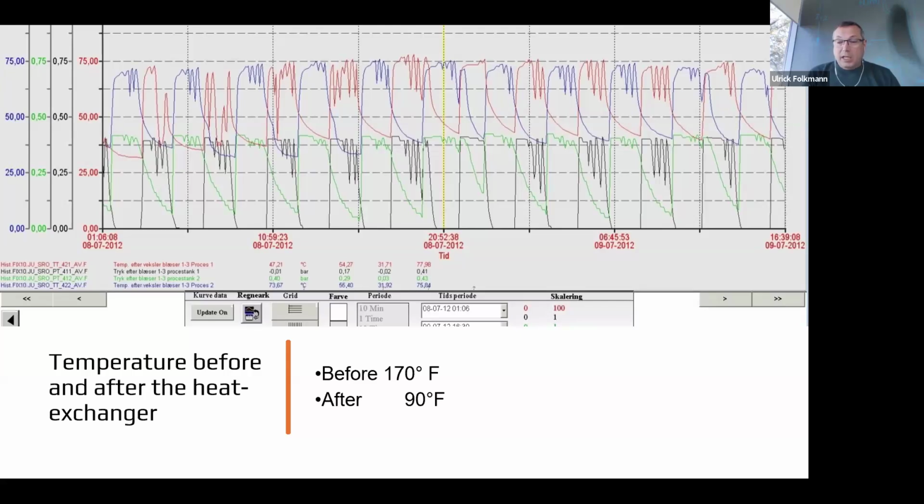We also have done some tests at a smaller utility where we thought, why not take it from the sewer system? We have tried so many different designs of heat exchanger for the sewer system, but we have not found the best way to use it. They will always block. There is a lot of maintenance on it. So I cannot recommend it right now.